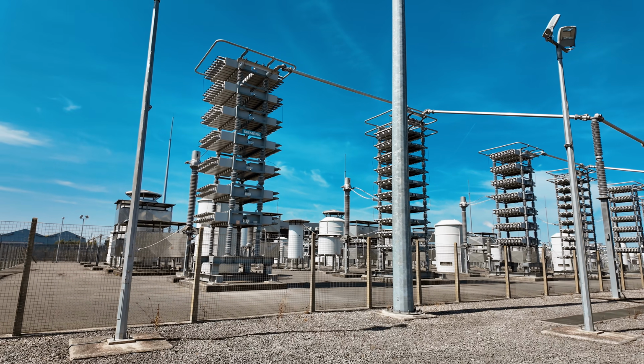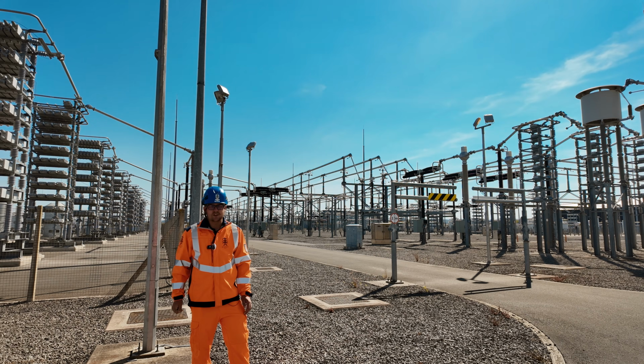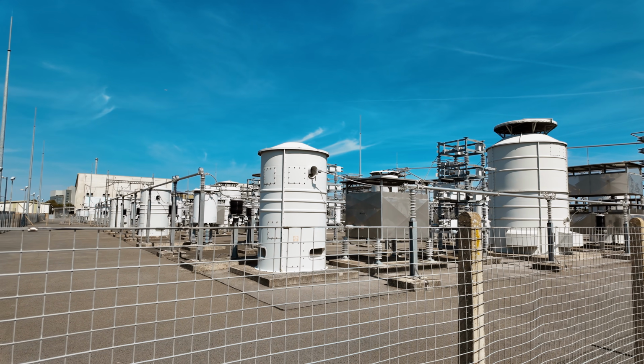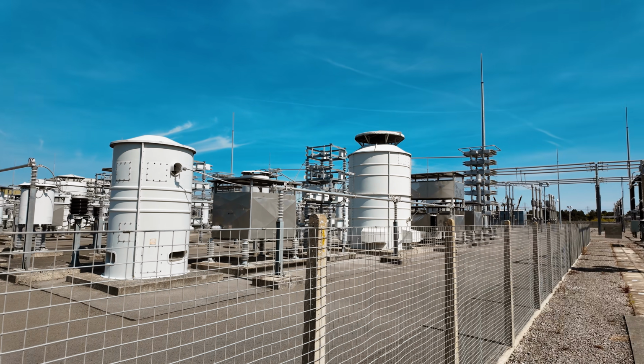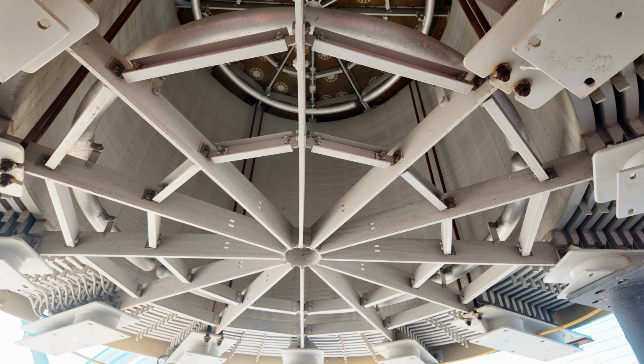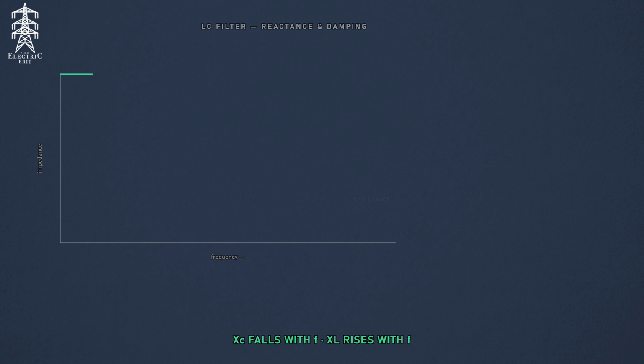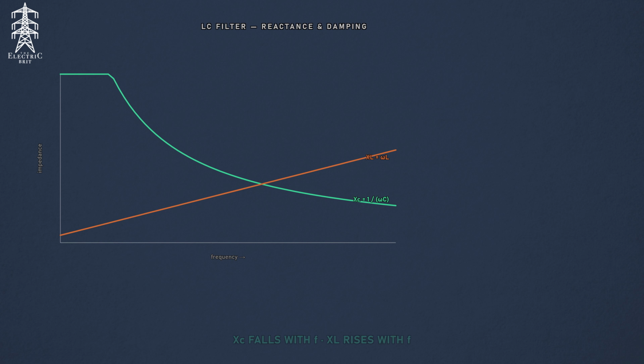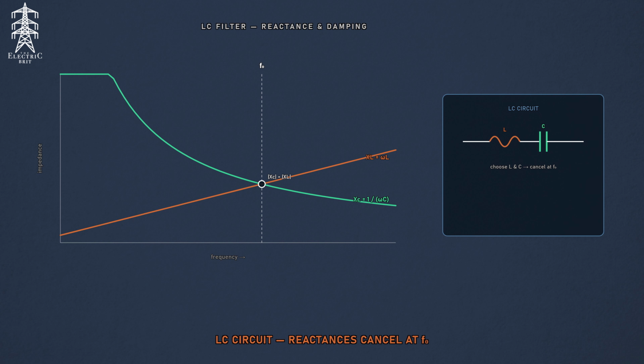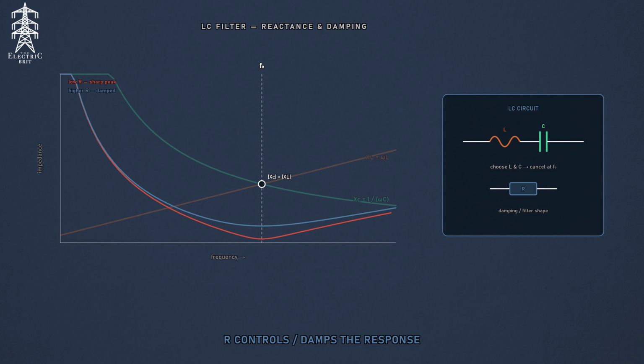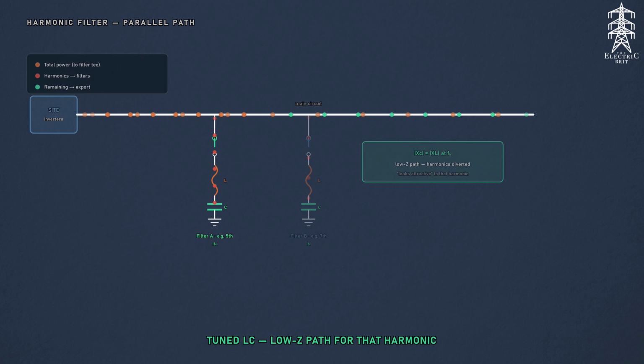The capacitors in our case is this big bank, which provides capacitive reactive power. We also have that massive air-cored reactor we mentioned, which is an inductor, with a specific inductance determined by the amount of coils of wire in there. The capacitor's impedance falls as frequency rises, whereas the reactor's impedance rises with frequency. Put the capacitor and reactor together and we get an LC circuit. By choosing their values, we can make their reactance cancel at a particular frequency. Resistance can then be introduced to control or dampen the response, depending on the type of filter. The capacitor and reactor are set so they cancel out, creating a path of low impedance for the harmonics they're tuned for, making it look really attractive.